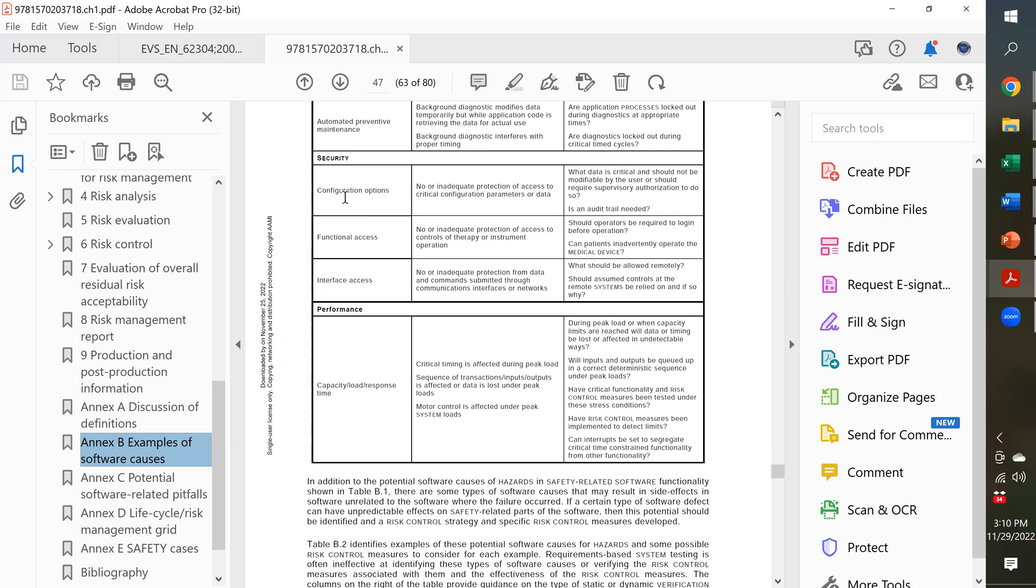So, you need to make sure that you've thought about all of these thoroughly and documented your justification for why it's not applicable or included in your hazard analysis. If it's not applicable, it would make sense in your hazard identification document to say, we consider the possibility of security hazards, but we don't believe these are applicable and here's why. Provide a justification. That's the right way to do this. So, make sure that you go through each one and explain why it's not applicable or included in your hazard analysis.